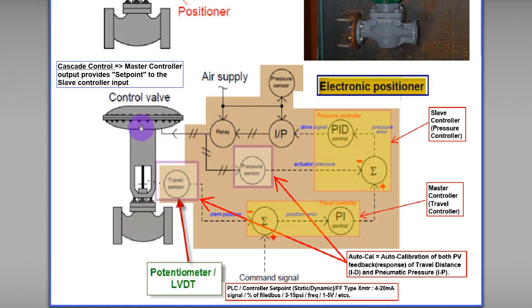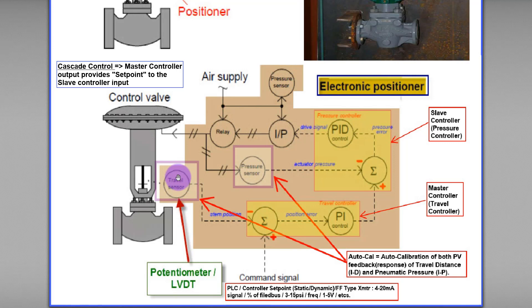This pneumatic pressure causes the control valve stem to move up and down based on the set point given by another controller such as a PLC. The movement of the control valve stem is measured by the travel sensor located inside the positioner — a potentiometer or LVDT (Linear Variable Differential Transformer). This travel position process variable is then fed back as input to the master controller, completing the cascade control loop. This is the basic principle of operation of an electronic positioner.